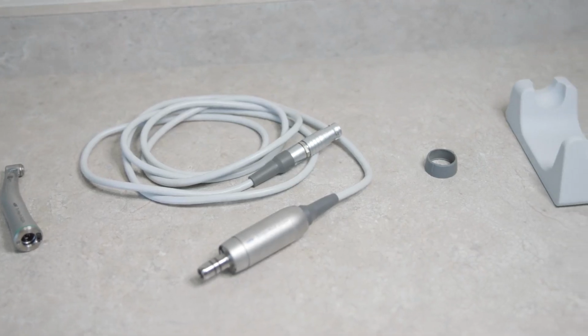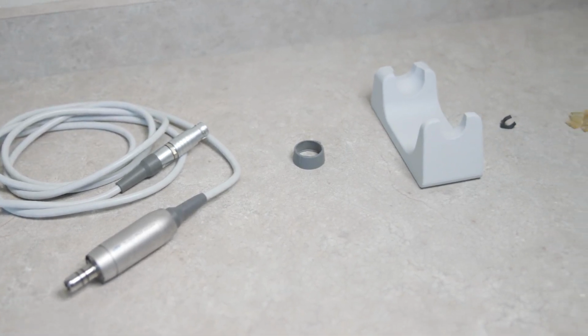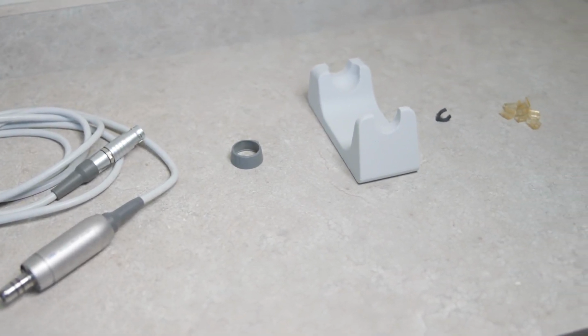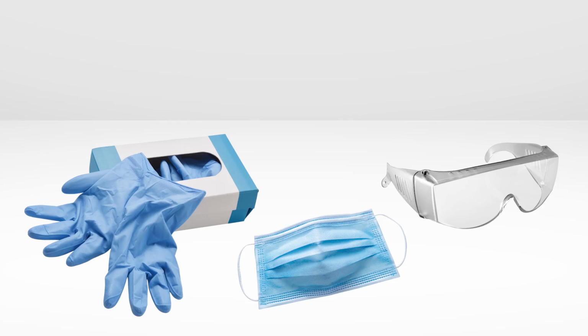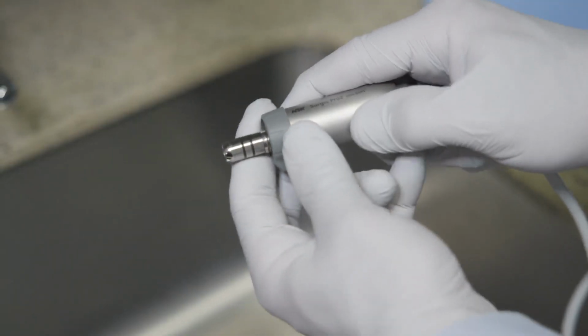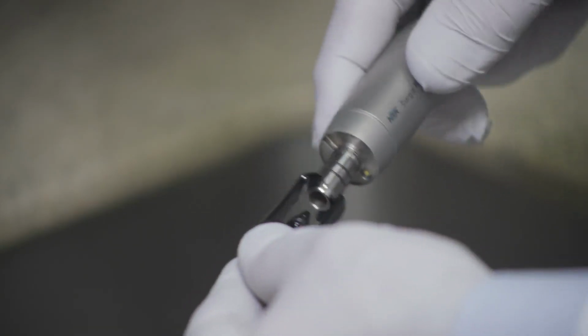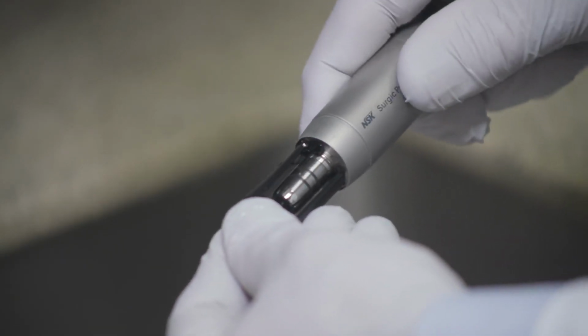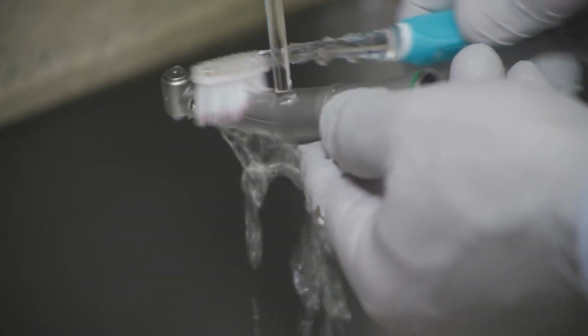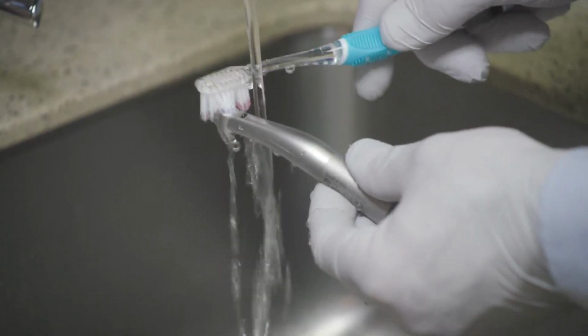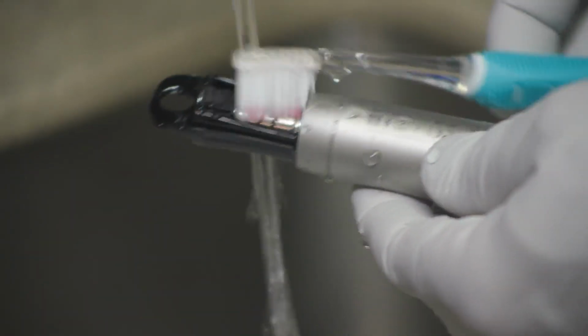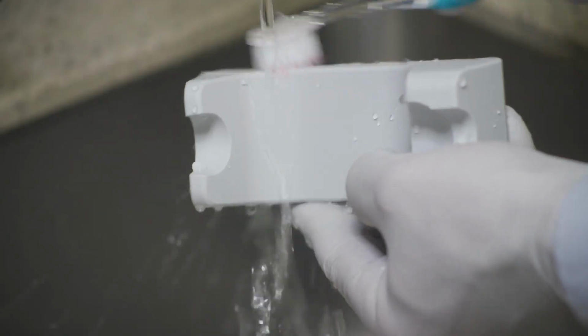For the motor and cord, tube holder, handpiece stand, and irrigation tube holder clips, follow these steps. Always use personal protective equipment before starting the process. Remove the gray tube holder. Attach the black protection plug on the motor and cord. Clean the surface of the products under running water at about room temperature with a soft toothbrush. 1 minute for the motor, 15 seconds for the holder and the handpiece stand.